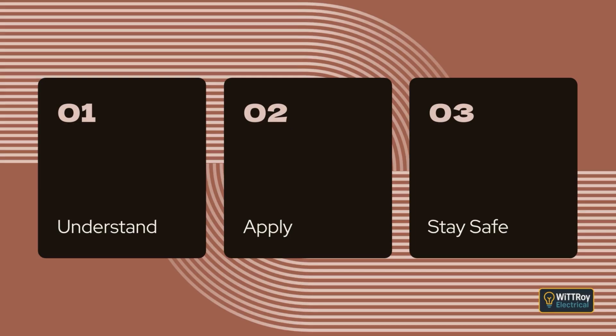Clause 1.5.10 Protection against earth fault currents. Any earthing conductor, or any part of the installation that is expected to carry earth fault current, must be sized and installed so that it can safely carry that current without overheating. In simple terms, the earthing conductors must be strong enough to handle the worst realistic earth fault. The conductor must not overheat, melt, or become damaged when a high fault current flows. This clause makes sure the earthing system remains reliable during a fault, so protective devices can operate correctly and disconnect the supply safely.